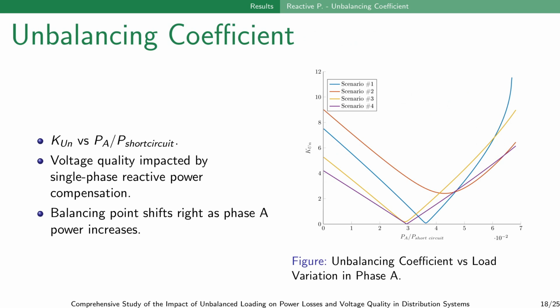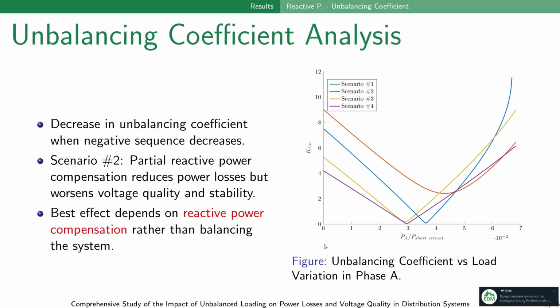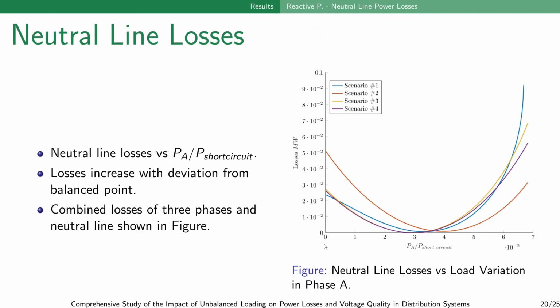The unbalancing coefficient versus phase A power ratio is shown here. Voltage quality is significantly impacted by single-phase reactive power compensation, with the balancing point shifted as the phase A power increases. The unbalancing coefficient decreases when the negative sequence decreases. In scenario 2, partial reactive power compensation reduces power losses but deteriorates the voltage quality and stability. The best effect is achieved through comprehensive reactive power compensation.